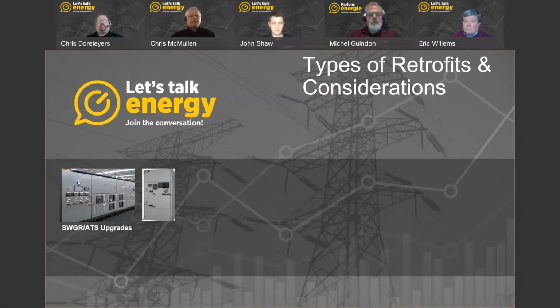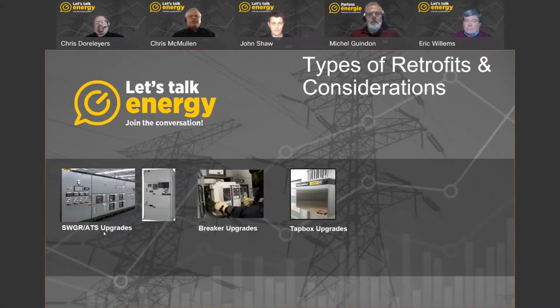Tap box upgrades. Tap boxes, or connection boxes, are a great addition to a system with hard to access connection points in the facility, either for load testing the unit you have or potential connection of a roll-up generator for support while your unit is under repair. Often while utility breaker maintenance is done, a part of the facility can be powered via the connection box. We bid on a project not that long ago where a tap box provided load share interconnect control between the roll-up generator and the existing generators.